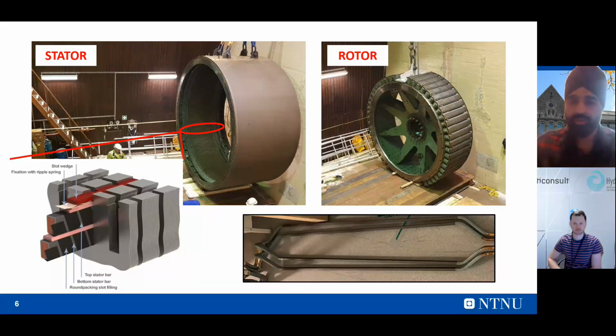So for that, we need regular testing of the end winding insulation, and we also need to take care of the layer we usually use at the end winding sites. Because of the turning of the stator bar at the end winding points, there is a huge amount of electric field stress at that point. So there we need to keep stress grading tapes, which we usually use for the protection of the stator bars at the end winding sides.